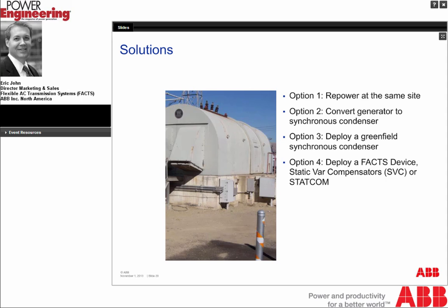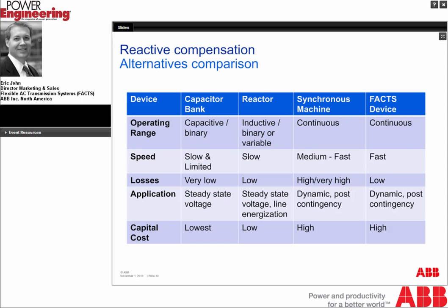And just to be fully complete here, we have a comparison of both static, meaning slow devices, and dynamic ones. And so the columns on the left, the capacitor bank and the reactors, are what we would refer to as a slow or a mechanically switched device.